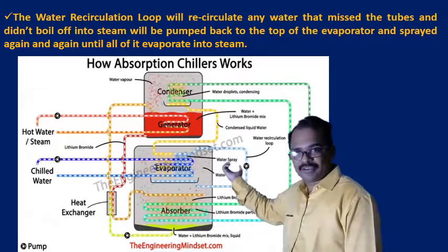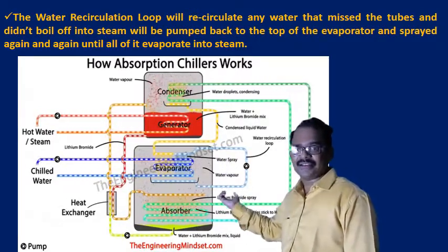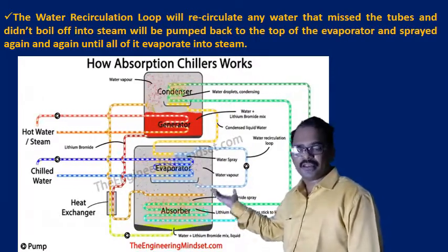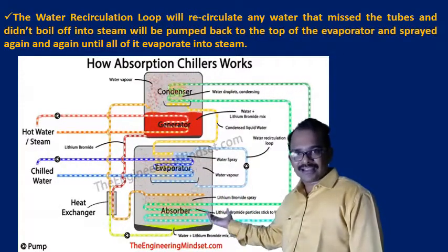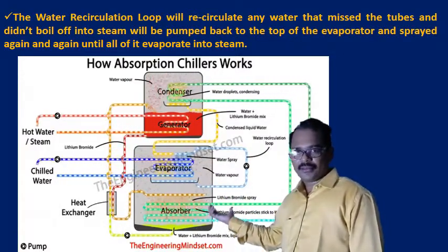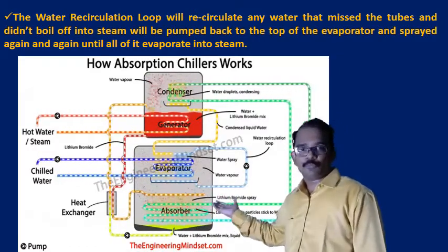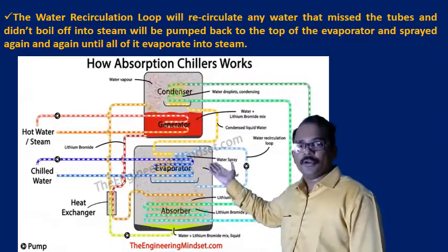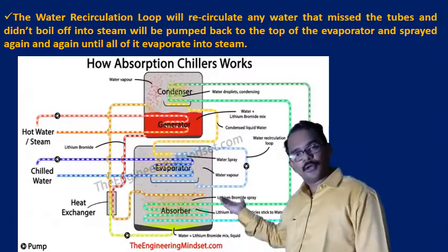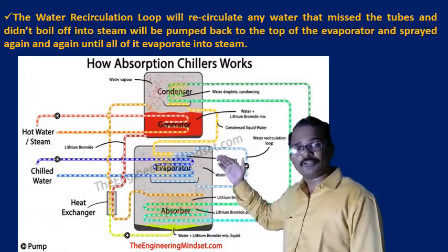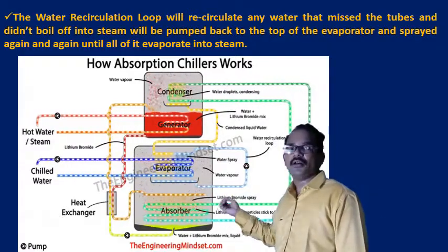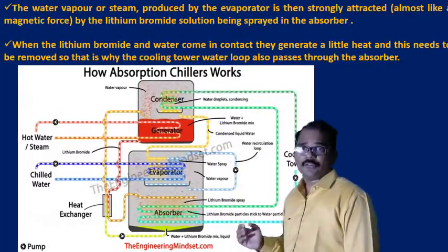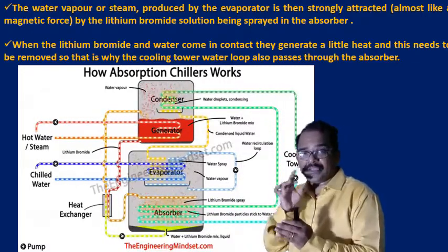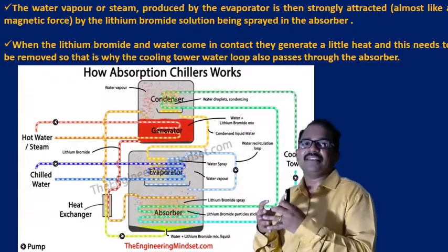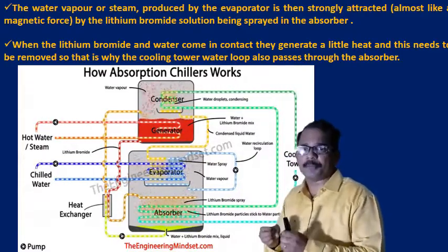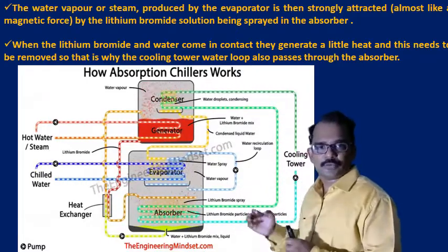It's very simple, right? Whatever water is coming from the condenser that didn't pass through the chilled water tubes, or which escapes the chilled water tubes, will be collected in the tray inside the evaporator, and that water will be sent again to the top of the evaporator to be sprayed onto the chilled water pipes, so that water also will be converted into steam or water vapor, right? So the water vapor or steam produced by the evaporator is then strongly attracted by the lithium bromide solution being sprayed in the absorber from the heat exchanger, right? You can see it here, what we have seen.